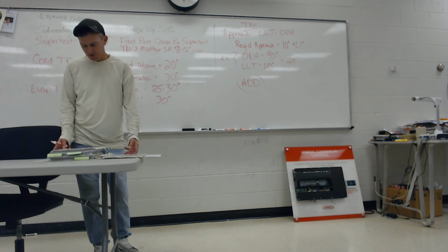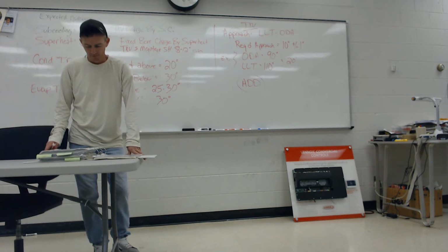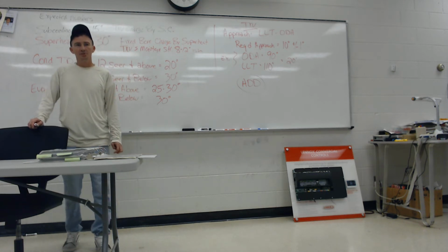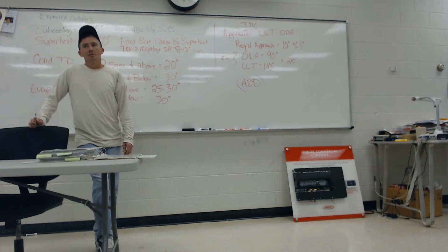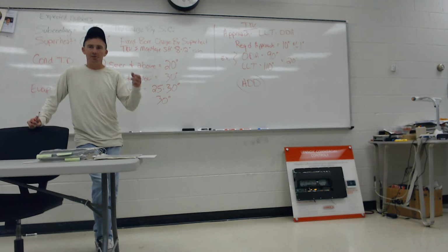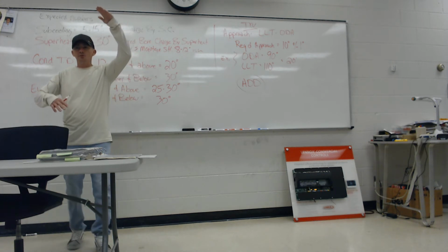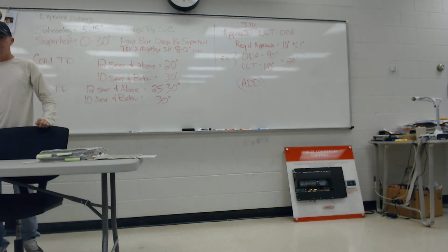Y'all remember compression ratio? We can talk about compression ratio for a second. Add 15 plus 15. High side plus 15, low side plus 15, and then divide them. Compression ratio, the higher the compression ratio, the more heat that's in that compressor. That's one thing you definitely need to know. With a higher compression ratio, you'll almost always have more heat in the compressor. Compression ratio equals heat.